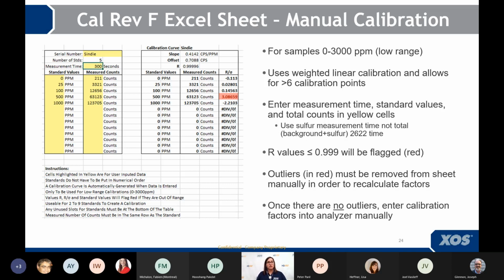on the right. So what you do is you enter the accepted reference values for your calibration in that first column, a yellow column. And then you enter the total counts time in the second yellow column, along with the measurement time. And then on the right, you'll see up towards the top, you'll see the calibration slope and offset, as well as the correlation coefficient and the residuals, okay? Like I said, the key feature of this sheet is that it does the weighted linear calibration, but it allows you to use 6 points, okay?